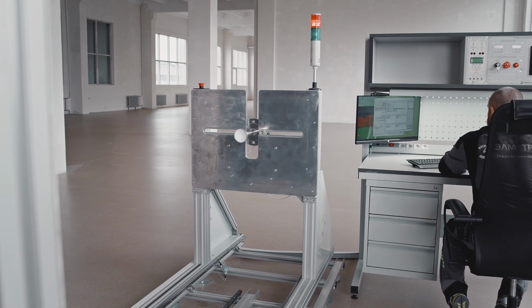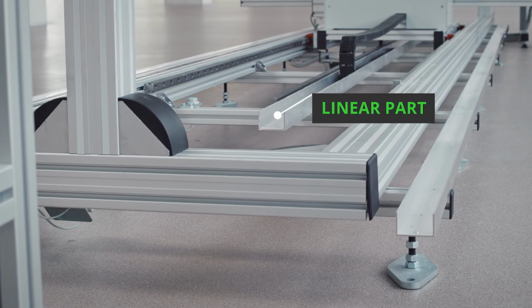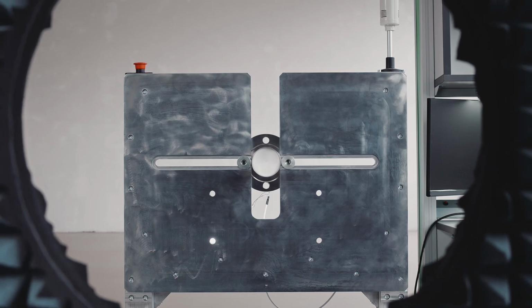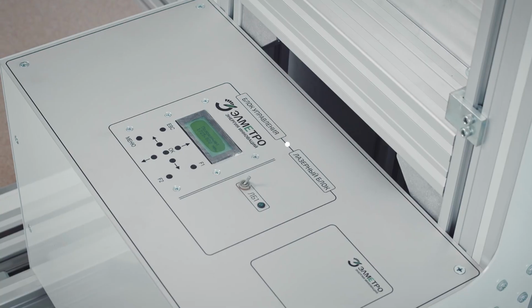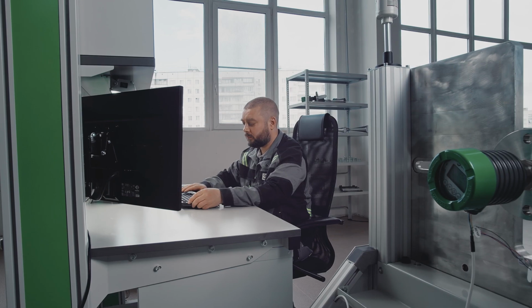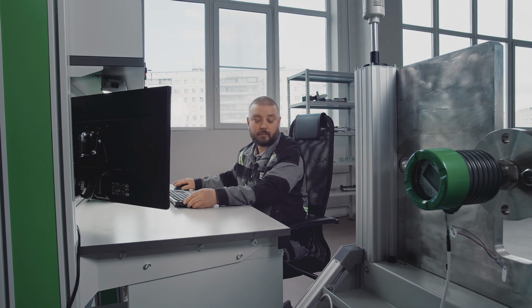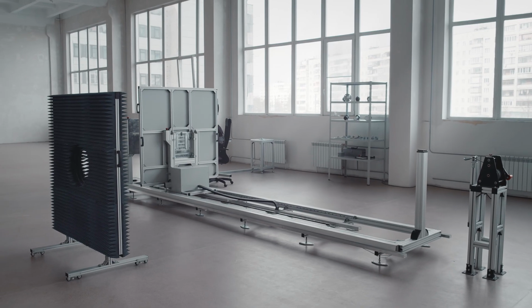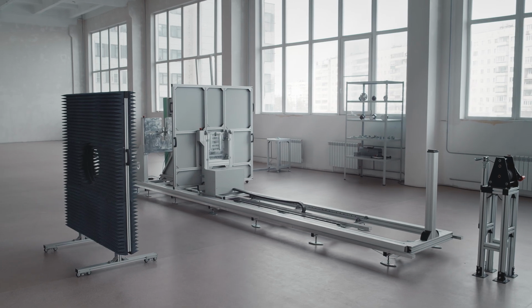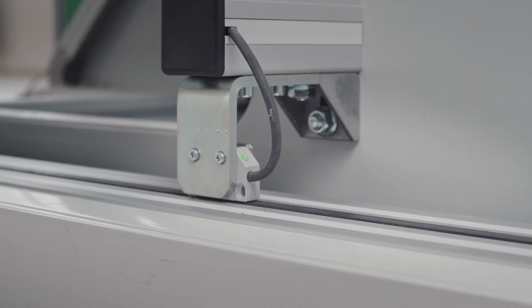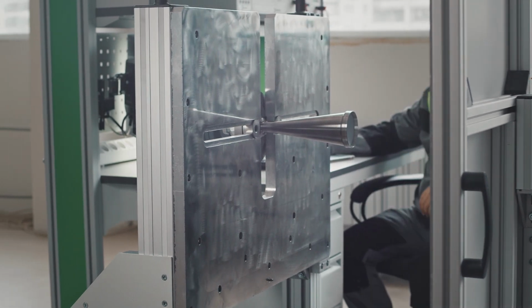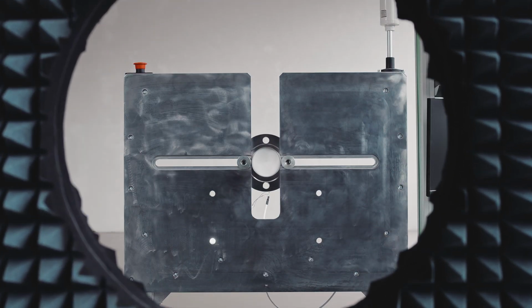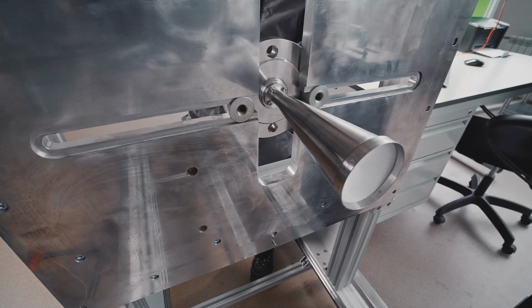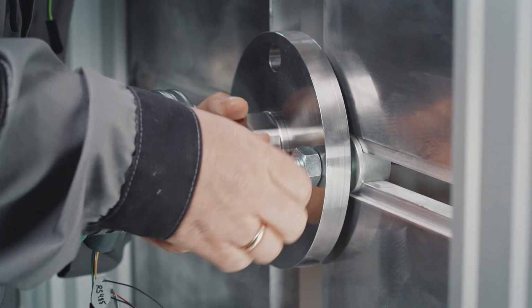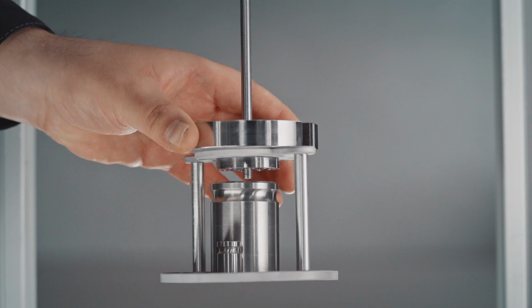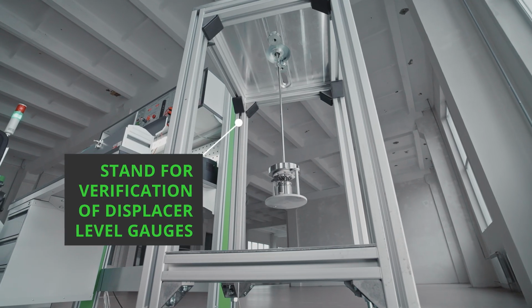Linear part of the bench is a metal shape with precision guides on adjustable supports. The linear part consists of the moving element that is displaced by the servo mechanism. The displacement of the moving element and its high-precision positioning are performed using the control software. The linear displacement transducer is used to determine the position of the moving element of the bench, having the reflective target against the fixed base. That is, the basement for placing the verified level instruments. Verification of displacer level gauges is organized on a separate stand.